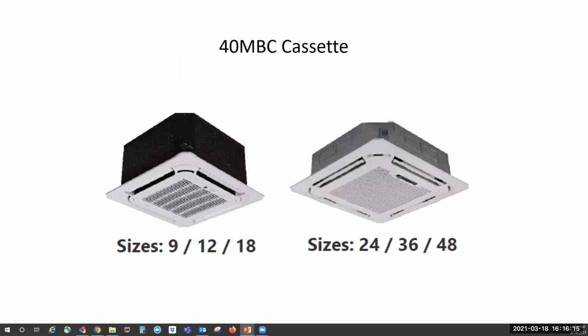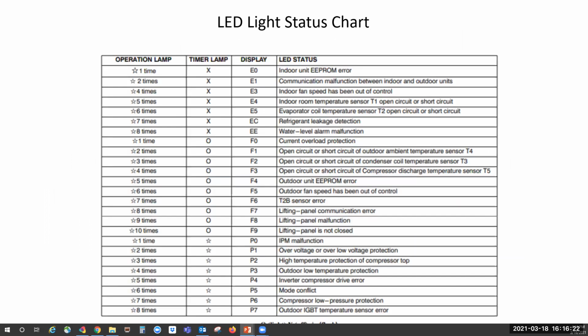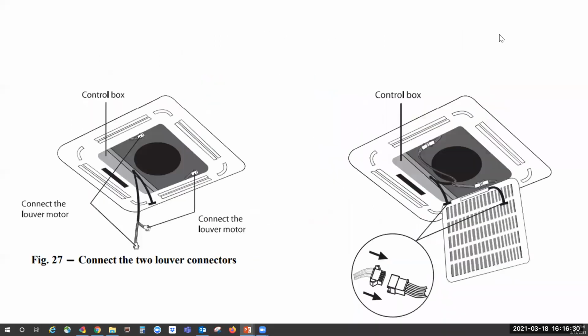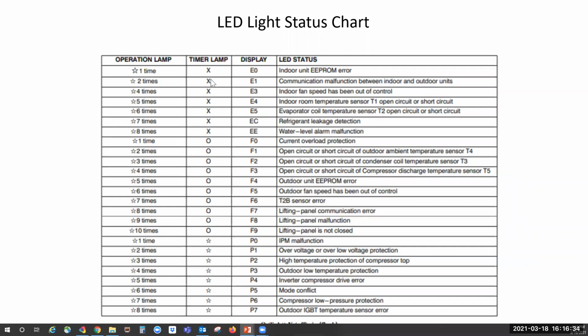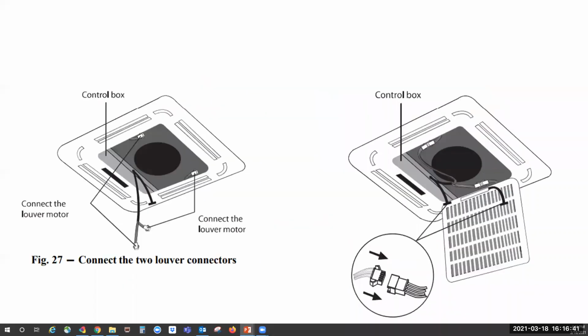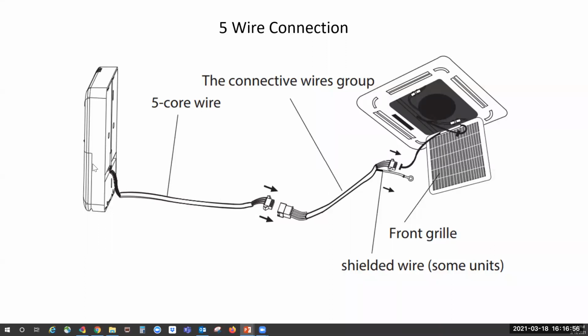The 40 MBC cassettes go in the grid ceilings. They have their own LED and fault codes on their status. And then when you're wiring in for the louvers, it's plug and play. Just plug it in, and then you have another wire that'll come from up here and come down to your wired wall controller. And these are communicating wires, so don't splice them. If you have to extend them, then you extend them with an extension cable.